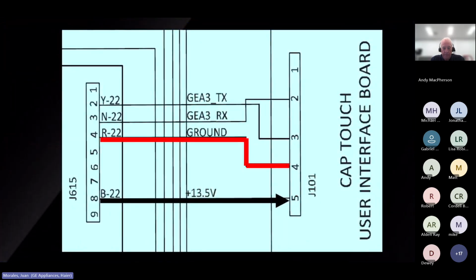That means you have that at the main. Now, you could also have 13.5 volts DC at the main and not at the UI, and that would be indicative of a bad wire harness. So it's a good idea to always ohm out the harness for continuity and make sure that whatever is going from one place is getting to the other. That's an important thing.